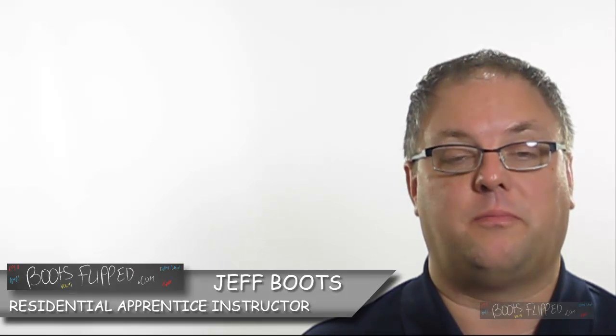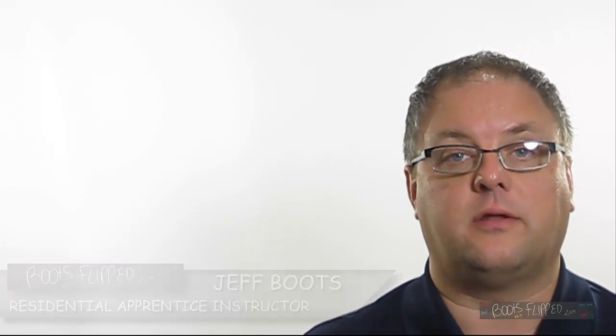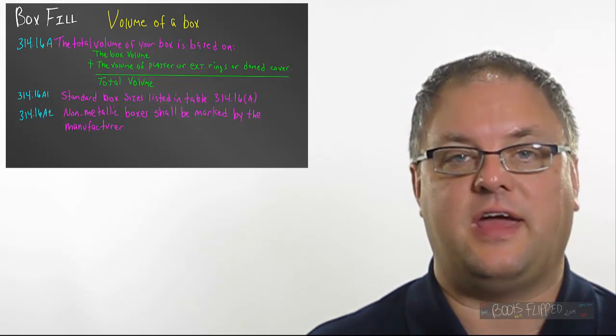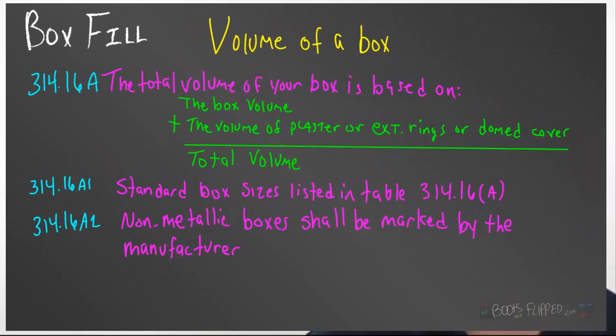Today we're going to talk about box fill and pull box calculations. In 314.16a, we talk about volume of a box. Now the volume of the box just isn't what is inside the box as far as the cubic inch, but if we put a device ring or an extension ring on there and we add all that together, that will give us the total volume of our box.